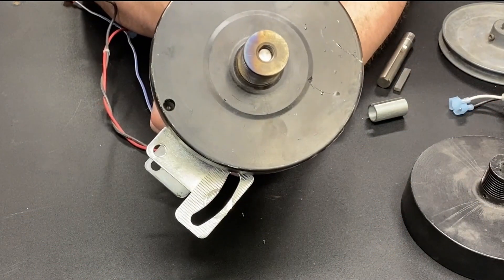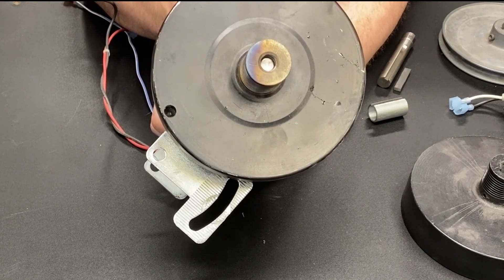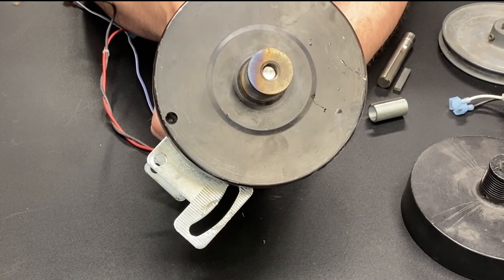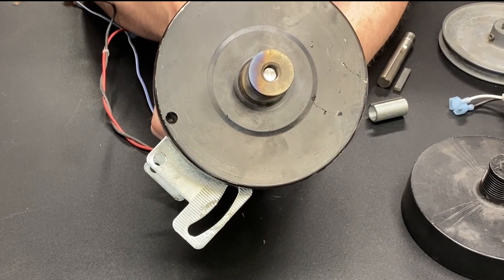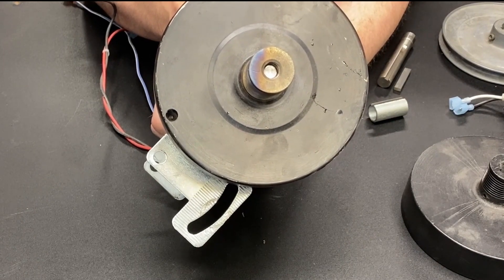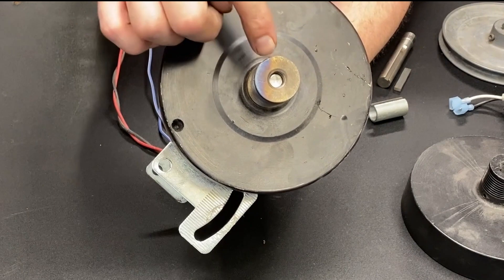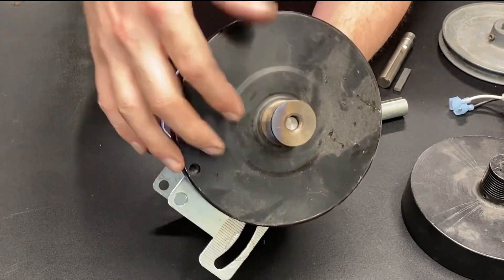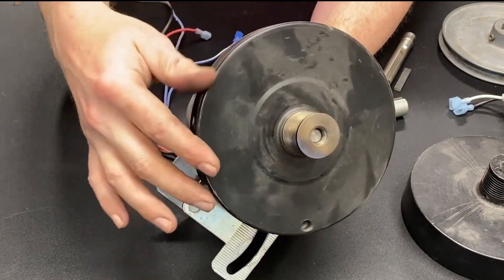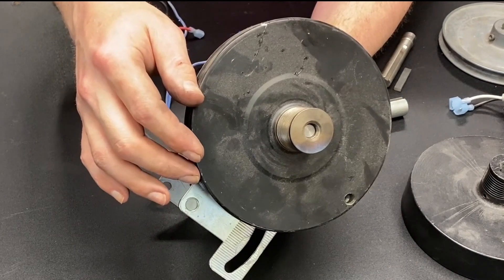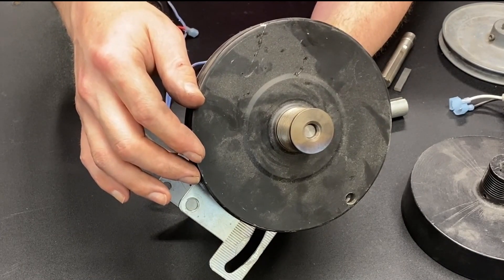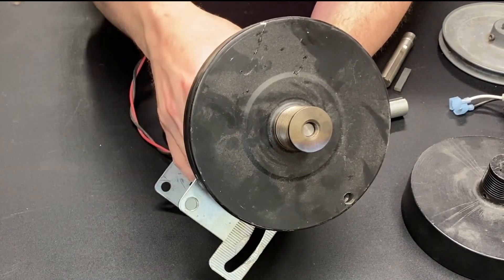The other thing that's important to know, if you have a thread-on flywheel, especially on smaller motors like the one in my hand, they are oftentimes Loctited in place. The only way to get them loose is to apply heat. You can see maybe on there a little bit of discoloration, where I hit that with a torch. After getting it fairly hot, I was able to spin it off.